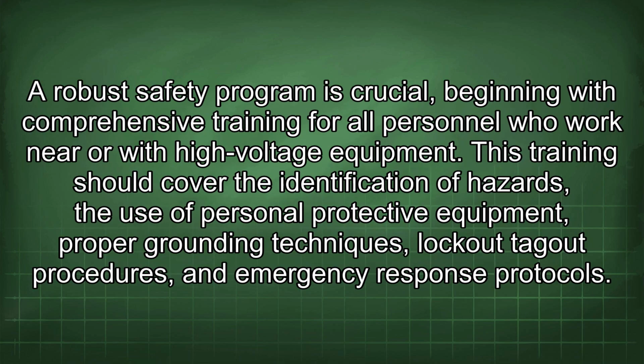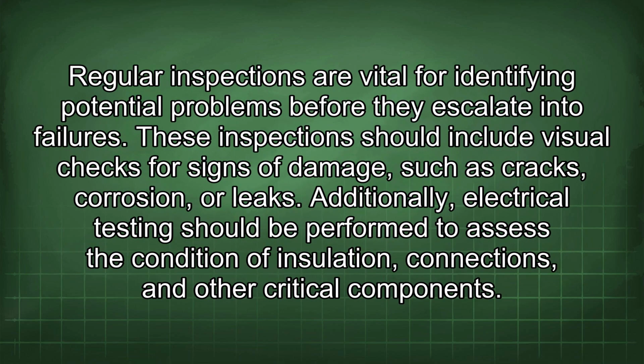A robust safety program is crucial, beginning with comprehensive training for all personnel who work near or with high-voltage equipment. This training should cover the identification of hazards, the use of personal protective equipment, proper grounding techniques, lockout-tagout procedures, and emergency response protocols. Regular inspections are vital for identifying potential problems before they escalate into failures. These inspections should include visual checks for signs of damage such as cracks, corrosion, or leaks. Additionally, electrical testing should be performed to assess the condition of insulation, connections, and other critical components.